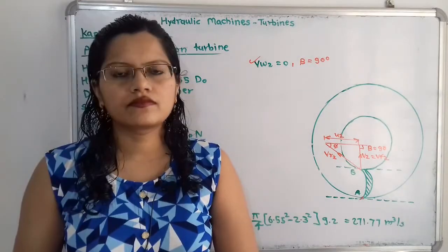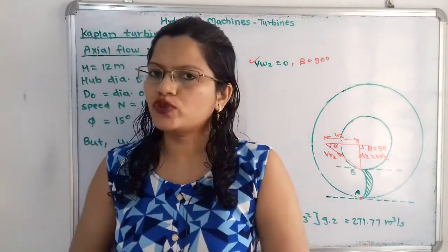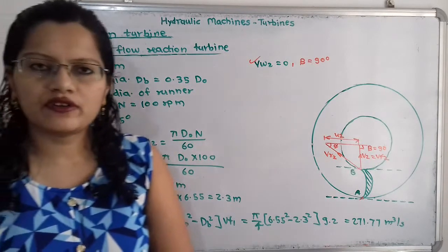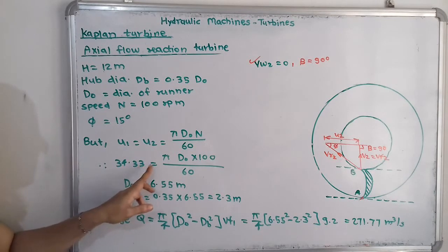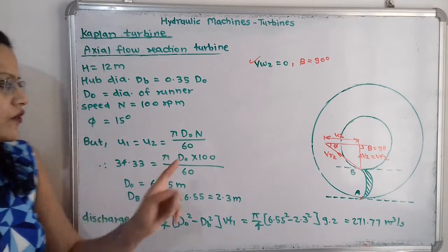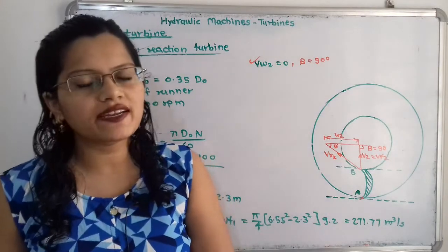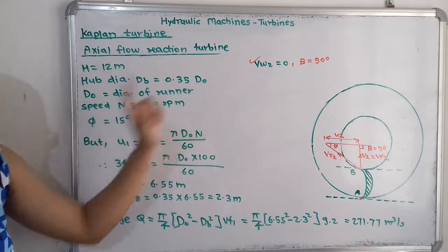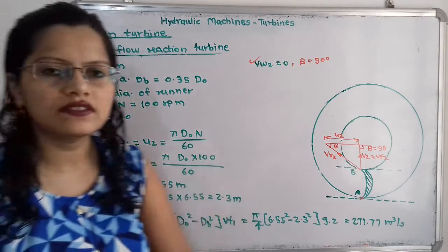For the Kaplan turbine, u1 = u2 = π × Do × N / 60. So 34.33 = π × Do × 100 / 60, giving the diameter of the runner Do = 6.55 m. From this, the hub diameter db = 0.35 × 6.55 = 2.3 m.